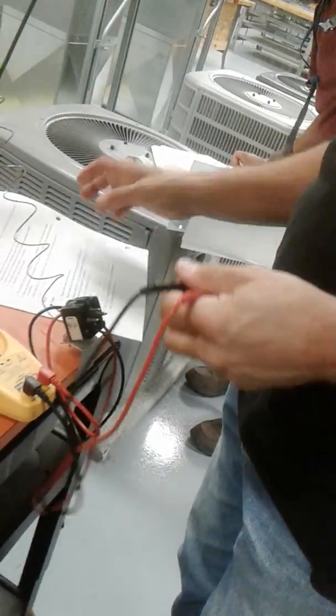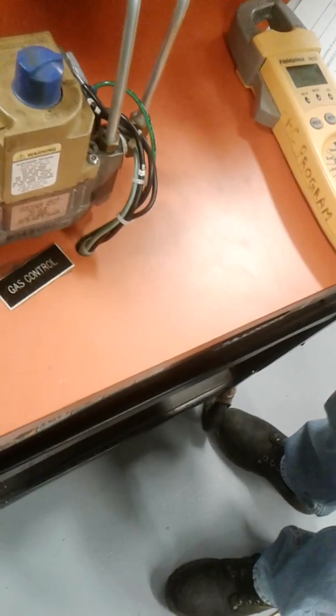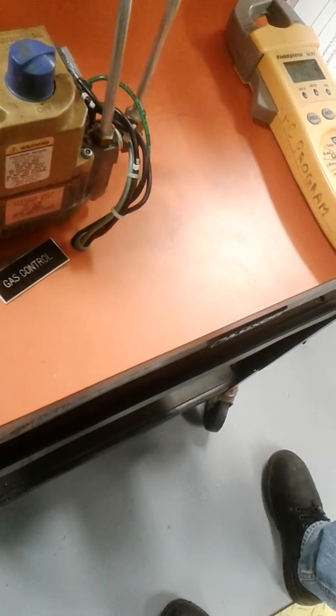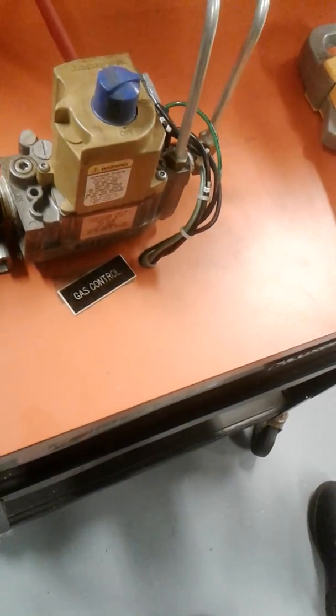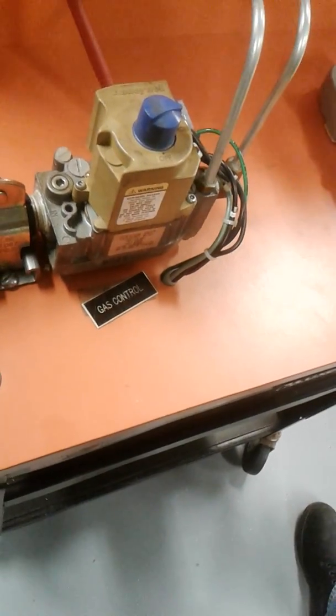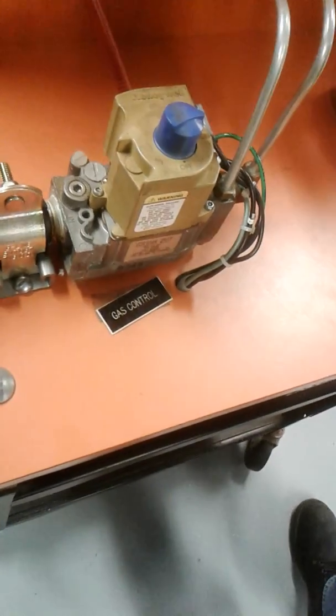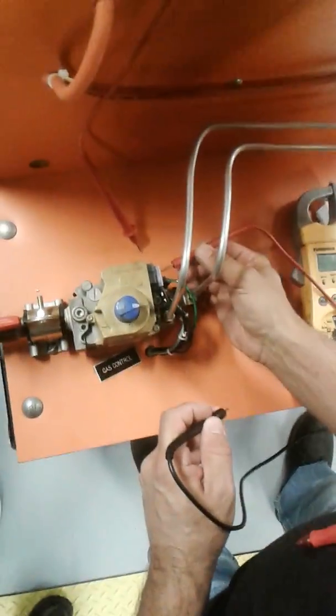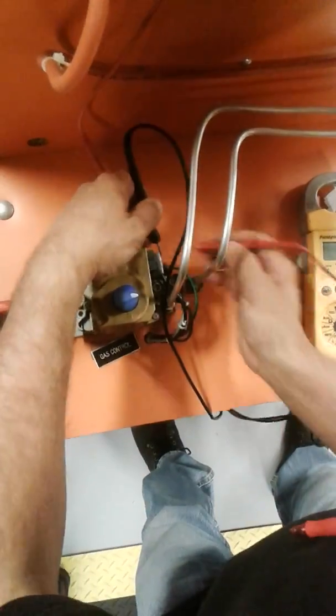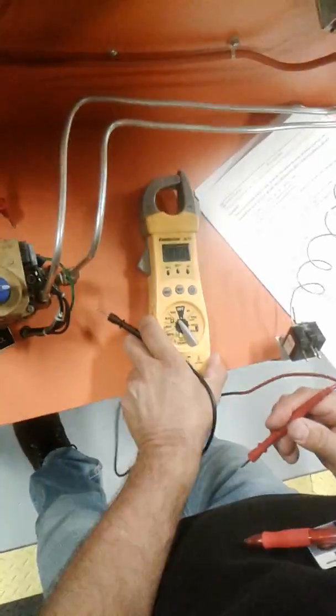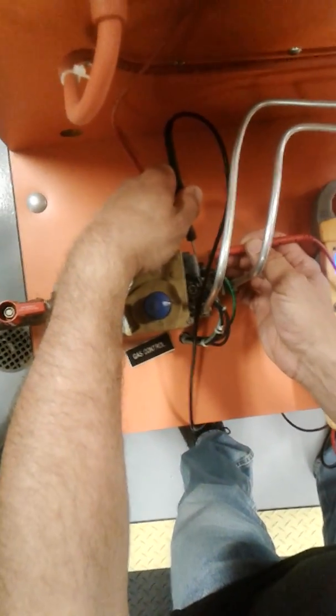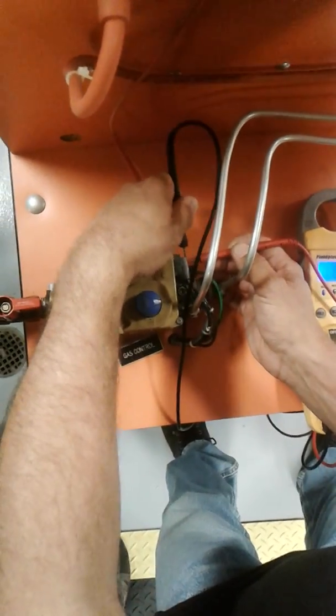The first thing I'm gonna do is go from MVPV to PV. The reason I'm going to PV is that's the pilot valve. We need a pilot first to light our burner, right? All right, let's check it out. Let's see if we've got voltage at our gas valve. I said MVPV is in the middle, and then the pilot valve is on the top. So let's set this to volts, okay? All right, I've got no voltage at the gas valve.